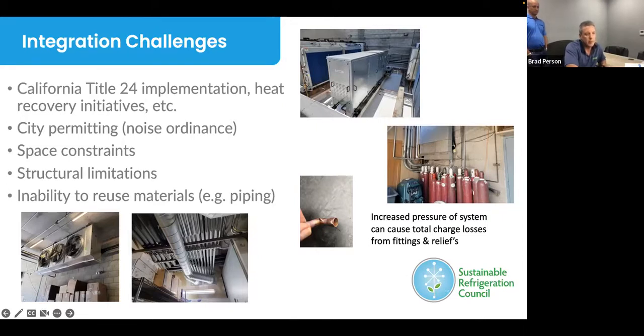So there's a lot to think about in the planning process. As we went through integration on these sites, in the design phase there's a lot of push with Title 24 and heat recovery initiatives that need to be utilized. So there are challenges in how to reclaim air and reclaim water. A lot of times you're dealing with equipment located a substantial distance from air handlers or rooftop units, so how do you mitigate the piping distances? In the bottom left picture, there's a coil we hung in the receiving area for air reclaim, to get in compliance with Title 24 and also to minimize the distance for piping the gas over for heat recovery.